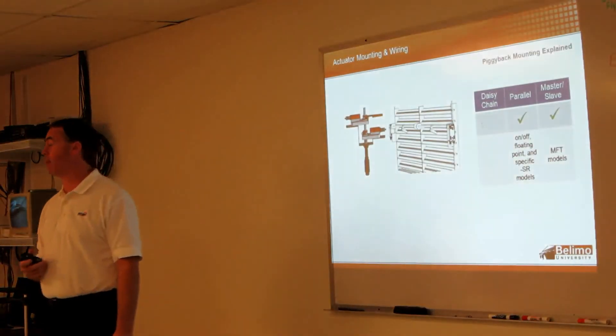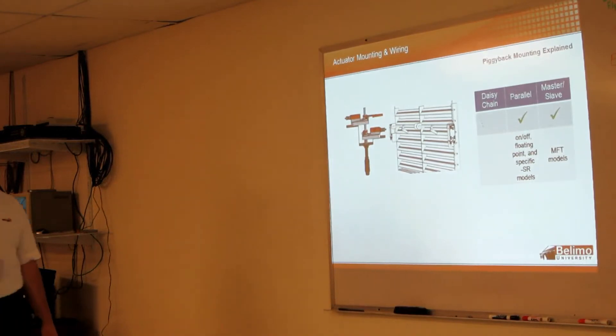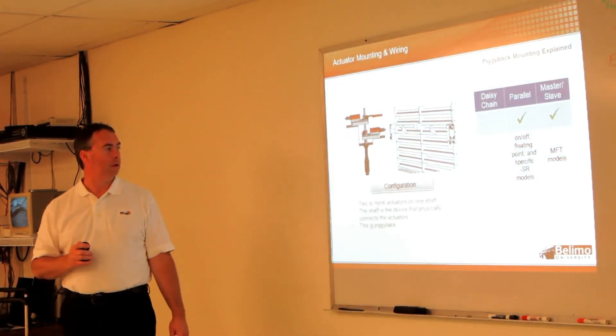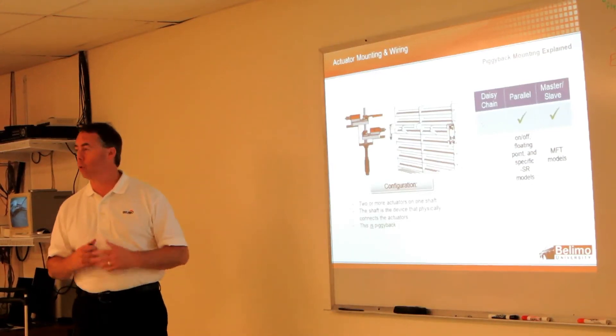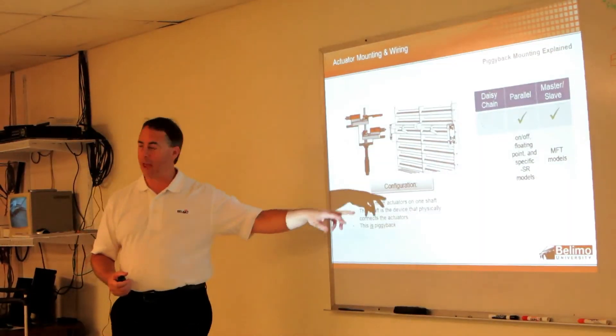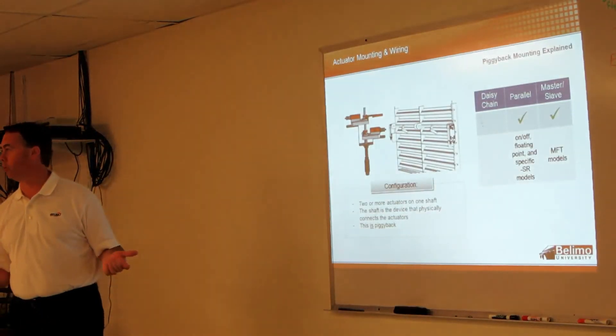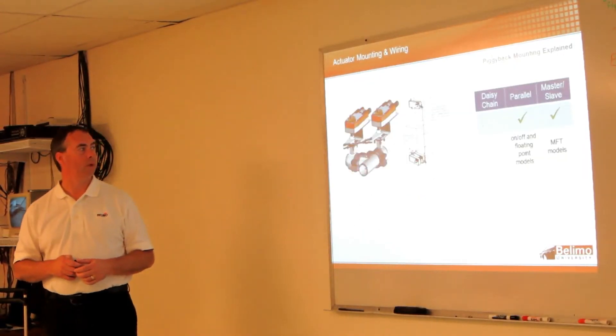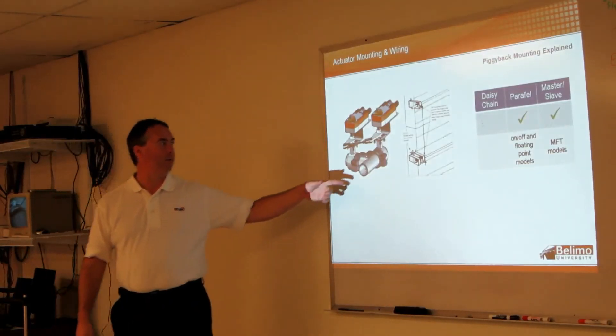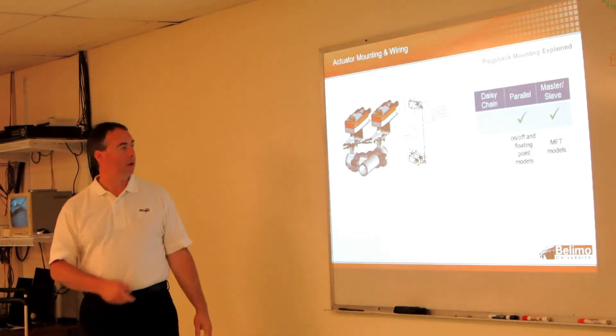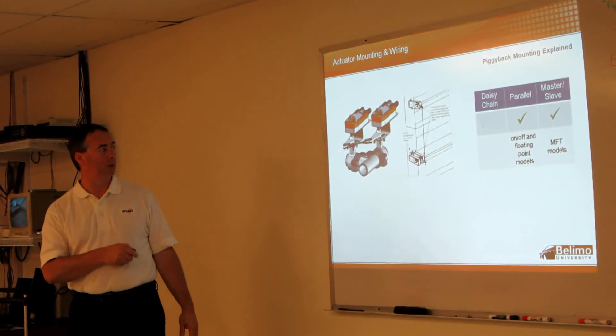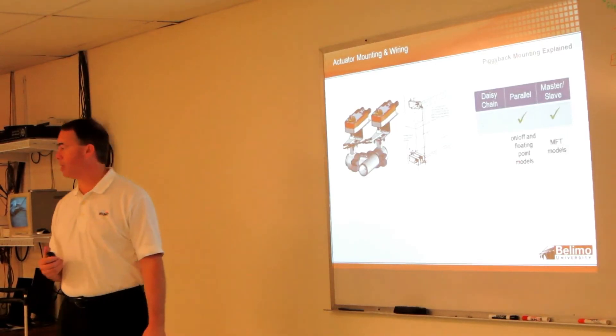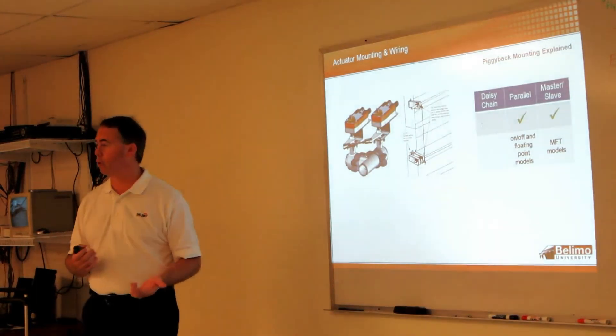We're going to want to master-slave the NFs. The rest can be wired up in parallel. Now this is the way we want to wire them if two or more of the actuators are mounted on the same shaft rather than on multiple shafts. And this is a case where, let's see, we have basically a butterfly valve set up. A three-way butterfly valve where we have a couple different actuators linked together but controlling two different shafts. And here, master-slave again, MFT models and parallel wire on-off floating point models.